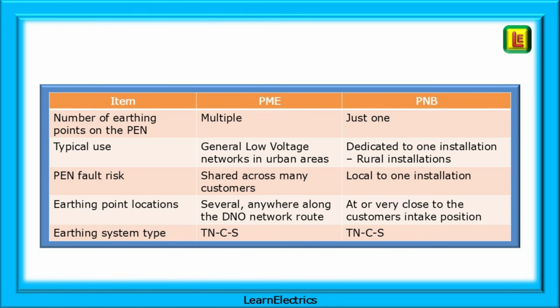The PME system will generally be used for low voltage networks in urban and built-up areas, whereas the PNB system will usually supply just one installation. A PEN fault in a PME system can affect several customers, hence the need for multiple earthing, whereas for PNB it is localised to just the one installation. PME, as the name suggests, has many earthing points along the DNO route, with only one for PNB. And importantly, they are both TNCS systems. They both use a PEN conductor.